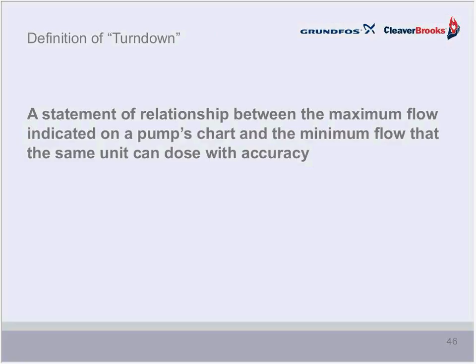We touched on turn-down a little bit ago. Now, turn-down, on the performance chart, is a very important concept with pumps. Technically, it is a stated relationship between the maximum flow indicated on the pump's chart and the minimum flow that the same unit can dose with accuracy. In other words, it is an indication of the maximum allowable reduction in flow rate performance while remaining accurate.